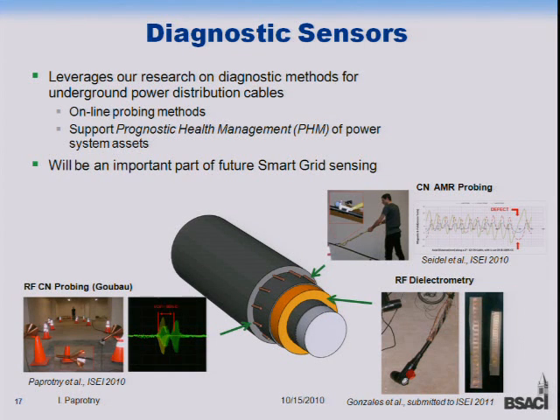We're looking at, if this actually shows your underground power distribution cable, the components here: a central conductor, with a semicon layer that smooths out the field. There's an insulating layer, the insulator, and then another layer of semicon again to smooth out the field. Then there's a shield of concentric neutral wires surrounding the insulator, which provides both the path for return fault current and a path for imbalance current. Then there's a jacket in modern cables.